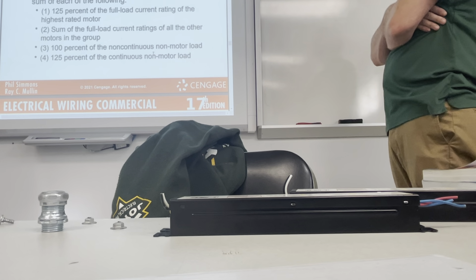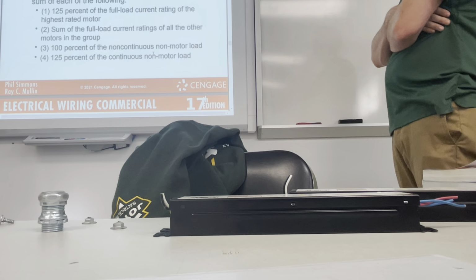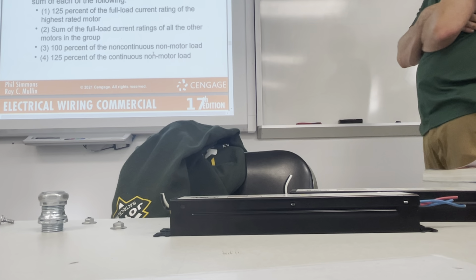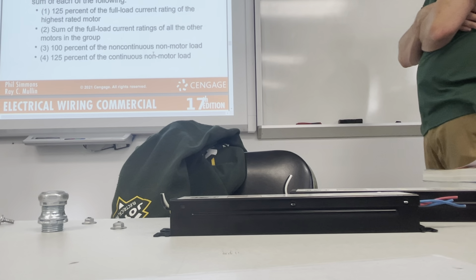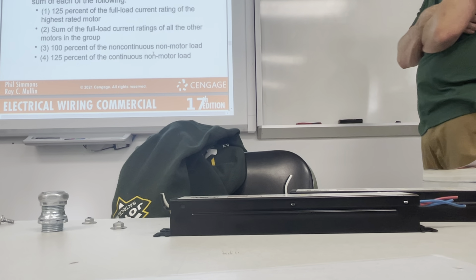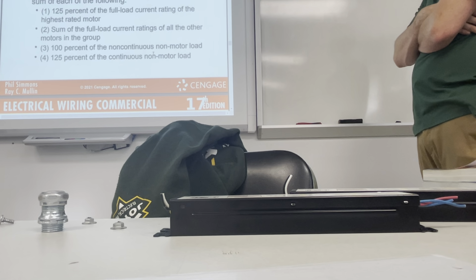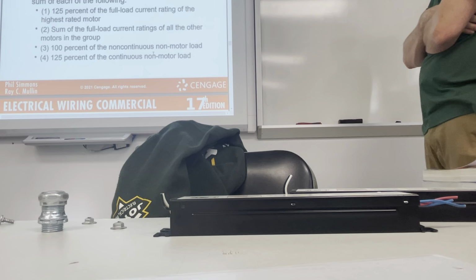Take this slide. Conductors supplying several motors. NEC 430.24 requires that conductors supplying several motors shall have an ampacity not less than the sum of each of the following: 1. 125% of the full load current rating of the highest rated motor. 2. The sum of the full load current ratings of all the other motors in the group. 3. 100% of the non-continuous non-motor load. 4. 125% of the continuous non-motor load.